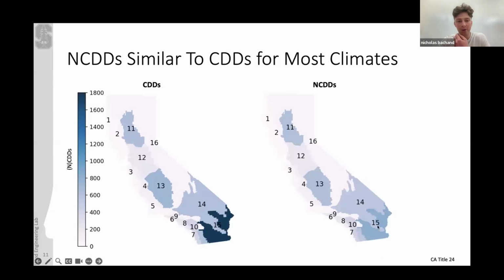And if we reapply this across California, it really is fairly similar. What this is saying is that most of these cooling degree days in California theoretically could be addressed with natural cooling, if that natural cooling was efficient enough. The one exception is climate zone 15, which still has the most natural cooling degree days of any climate zone, but there are so many cooling requirements, and the low temperature is not getting low enough in a lot of these days to support the cooling.